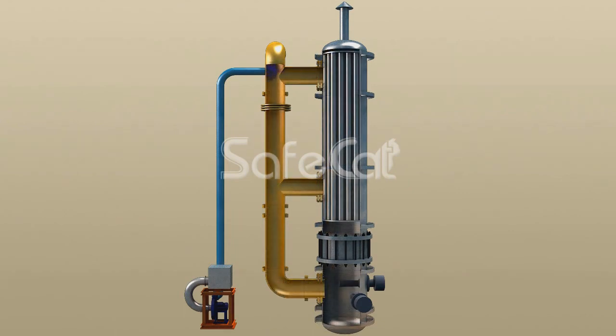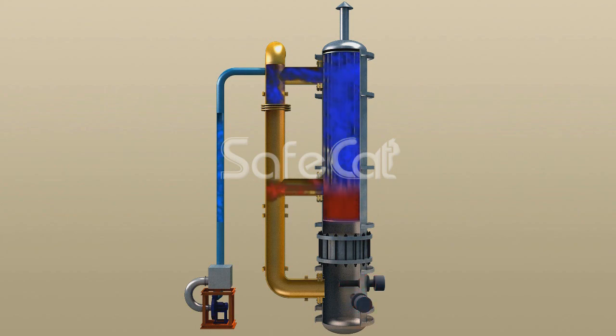The catalytic block is preheated with electric heaters on startup until reaching the reaction temperature necessary for hydrocarbon oxidation. Then the heaters are switched off, and the temperature is sustained by the reaction itself.